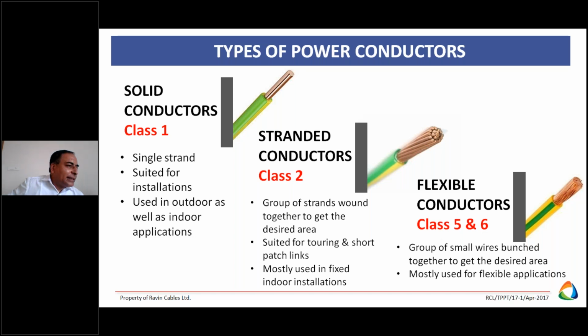In class 2, the minimum number of wires is defined, but the diameter is not defined. But in class 5 and class 6, the maximum diameter is defined. Let me give one classic example of flexible cable. In flexible cable, you find 0.2, 0.3 mm diameter of the wire. But in flexible, you can't use 1.5, 2.5 diameter. So for flexibility, if you want to increase the flexibility, reduce the diameter of the wire and increase the number of wires.